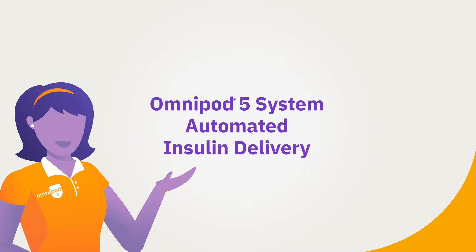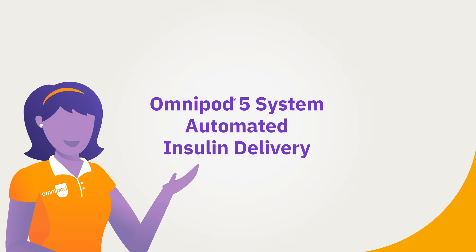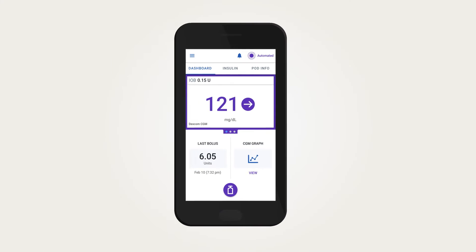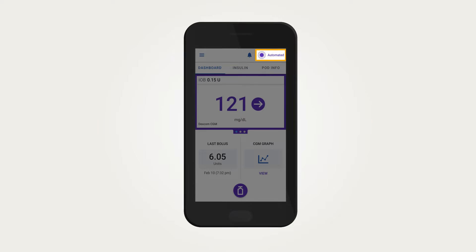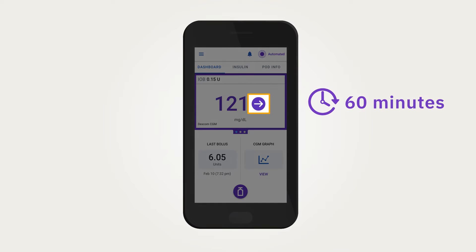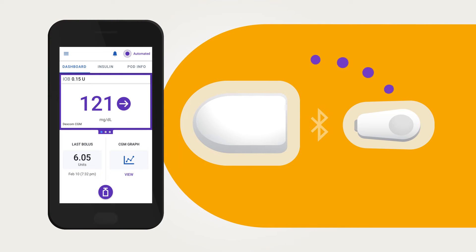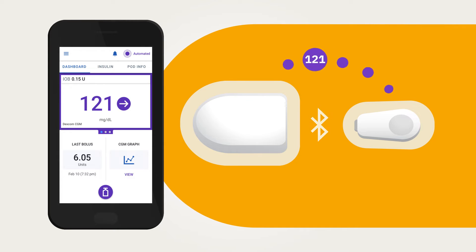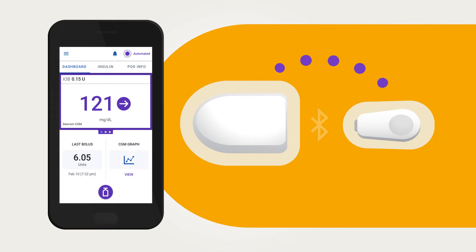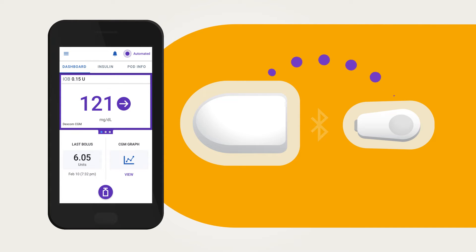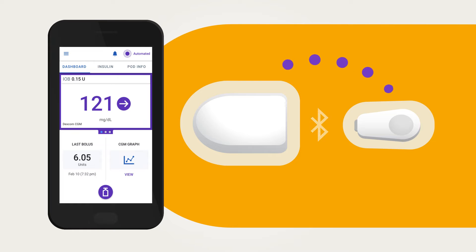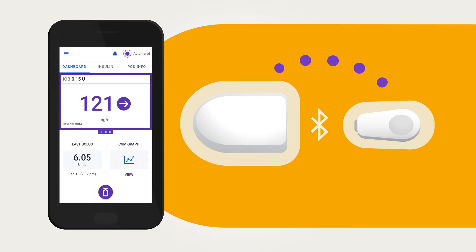Omnipod 5 System Automated Insulin Delivery. When the Omnipod 5 System is in automated mode, your basal insulin delivery will adjust based on what your sensor value is and where it is predicted to be 60 minutes into the future. The pod is enhanced with Smart Adjust Technology that receives values directly from the sensor to determine how much insulin to deliver every 5 minutes. The main goal of the algorithm, also known as Smart Adjust Technology, is to steer your sensor values towards your chosen target glucose to help you improve your time in range.